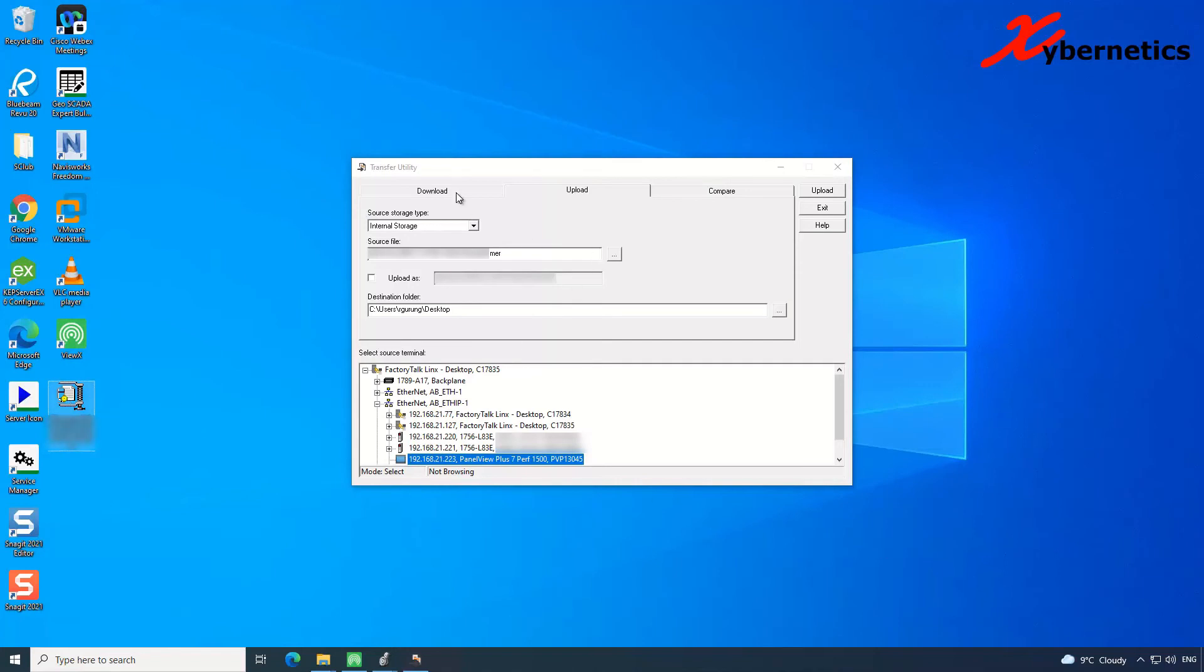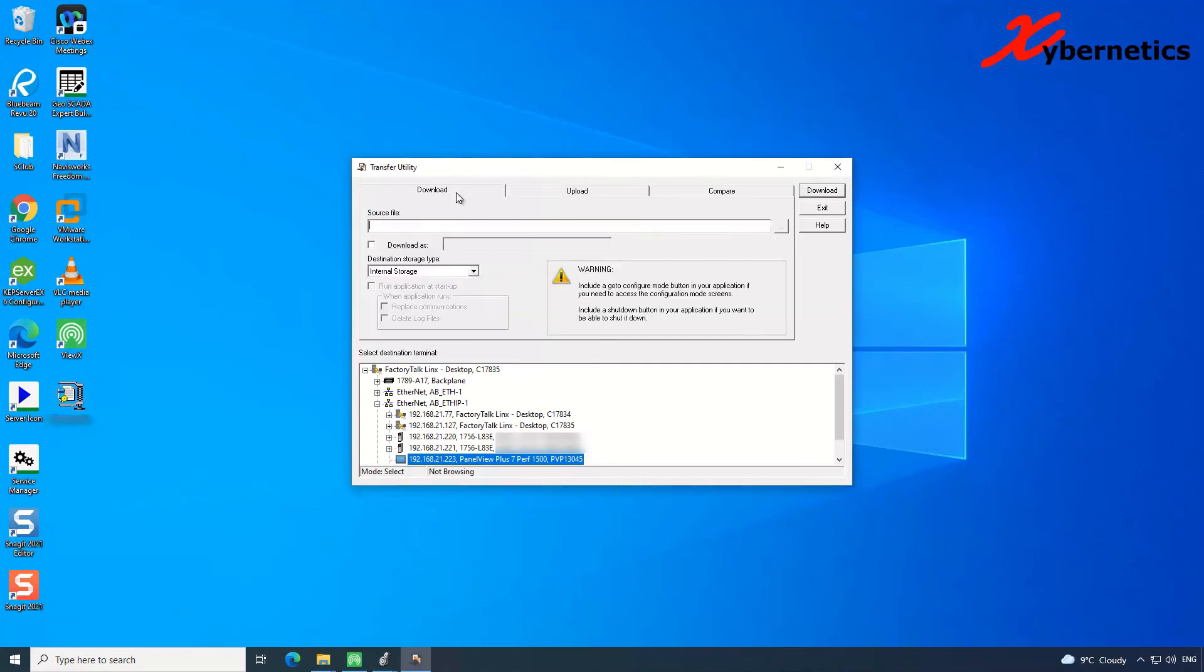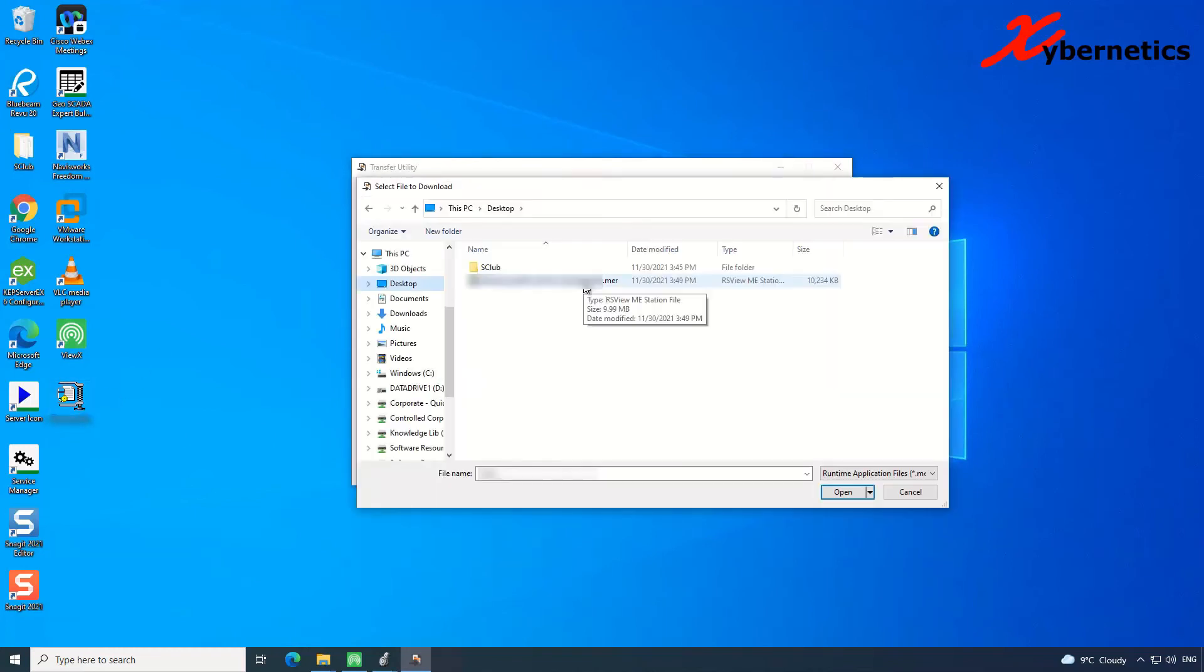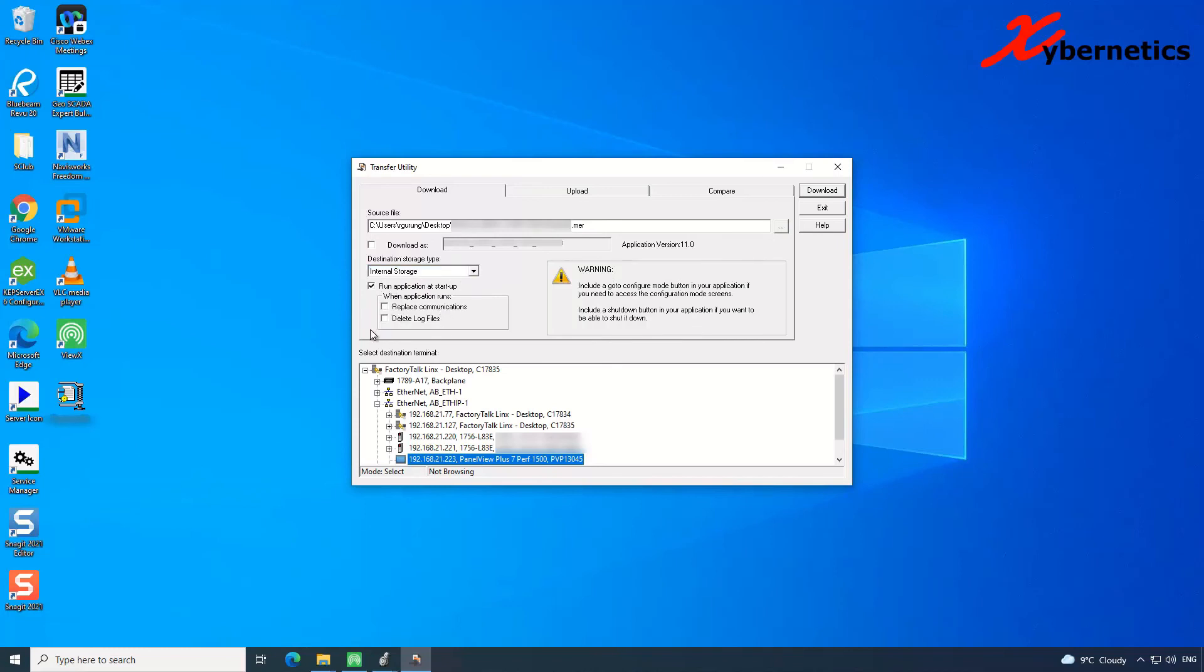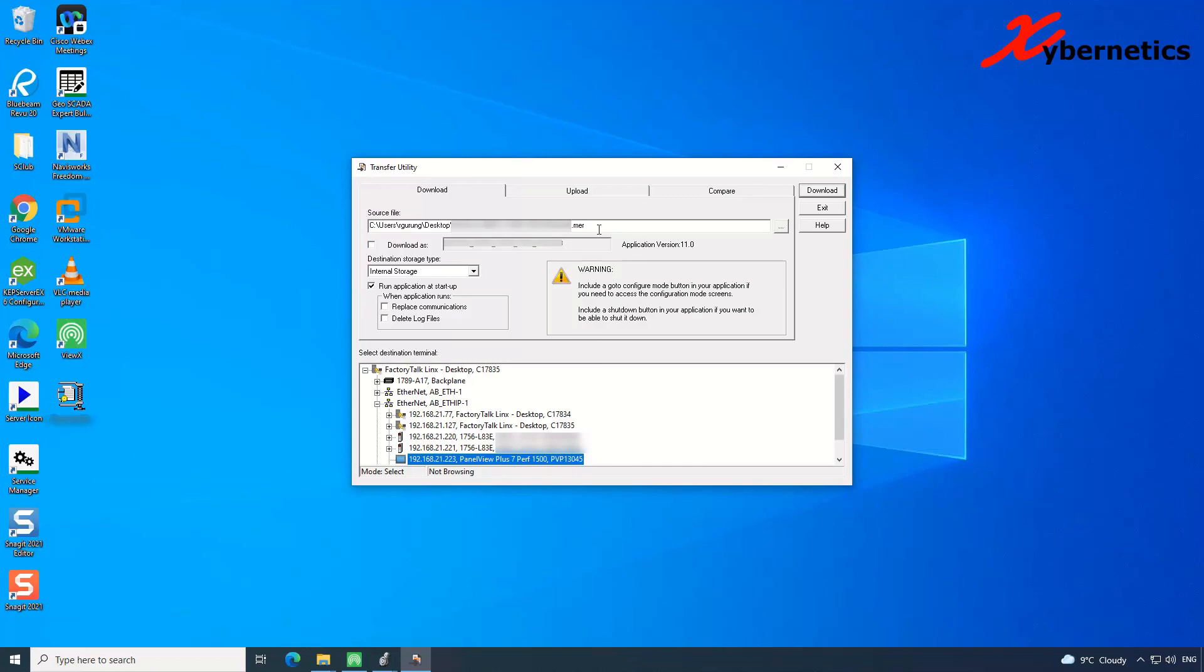Now if you want to push the same file back into your PanelView, you have to go to download. And this here, the source file will be your desktop, in here this MER file, and open. And destination will be the internal storage. That's where I'm putting it. And then you can click on run on startup, replace your communication driver and all that stuff. Once that's done, click on download. What this does is that it pushes this file into the PanelView and make sure you select the appropriate target again, whichever the appropriate PanelView you're trying to push the runtime file to.